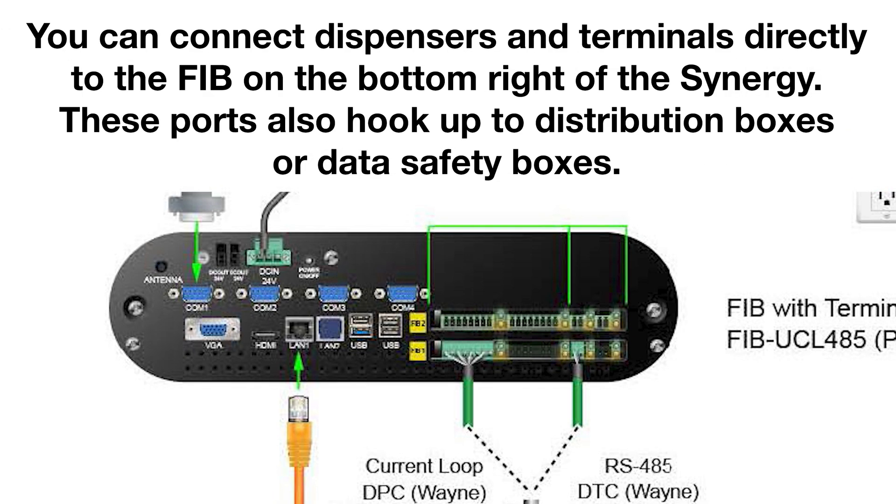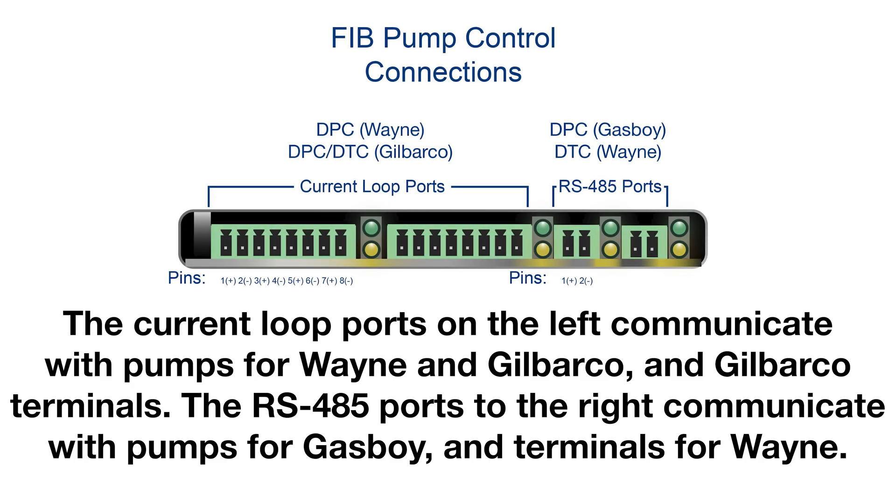You can connect dispensers and terminals directly to the FIB on the bottom right of the Synergy. These ports also hook up to distribution boxes and data safety boxes. These are the FIB pump control connections. The current loop ports on the left communicate with pumps for Wayne and Gilbarco and Gilbarco terminals. The RS-485 ports to the right communicate with pumps for Gasboy and terminals for Wayne.